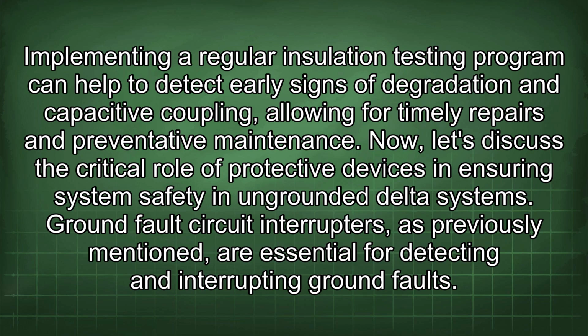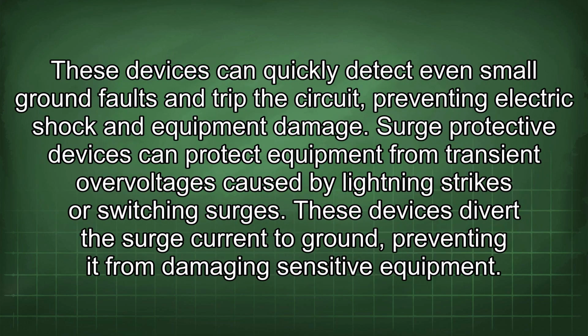Now, let's discuss the critical role of protective devices in ensuring system safety in ungrounded delta systems. Ground fault circuit interrupters, as previously mentioned, are essential for detecting and interrupting ground faults. These devices can quickly detect even small ground faults and trip the circuit, preventing electric shock and equipment damage. Surge protective devices can protect equipment from transient overvoltages caused by lightning strikes or switching surges. These devices divert the surge current to ground, preventing it from damaging sensitive equipment.